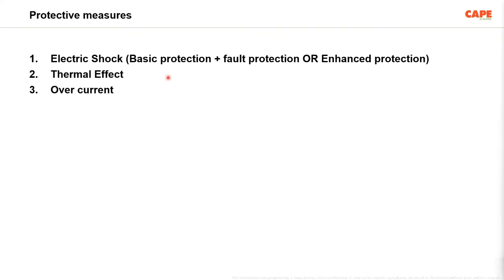So like that, a combination of protective measures are required for thermal effect. Also, a combination of protective measures are required for overcurrent. Overcurrent, say for example, whenever in the standards or technical books it is written as overcurrent, you should think that it is an overload current or a short circuit current. Both are together called overcurrent.